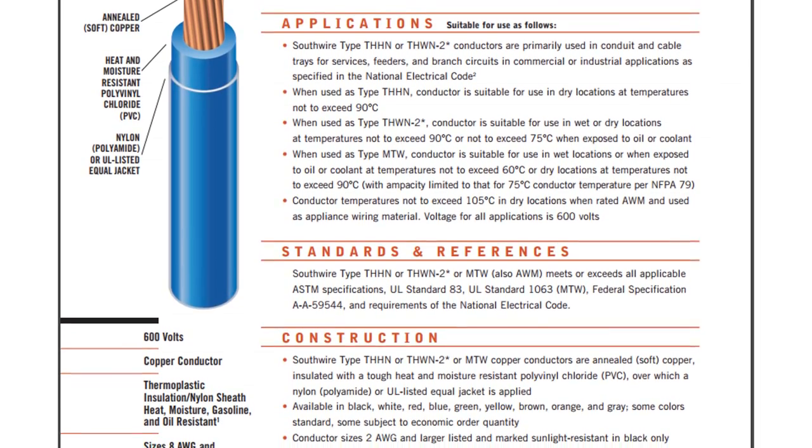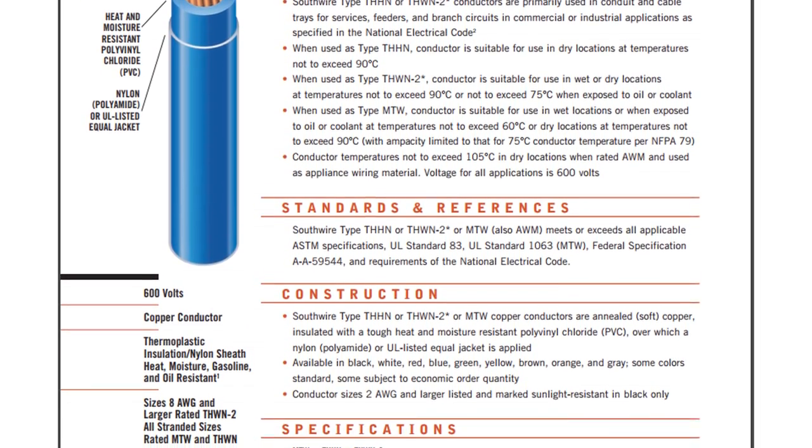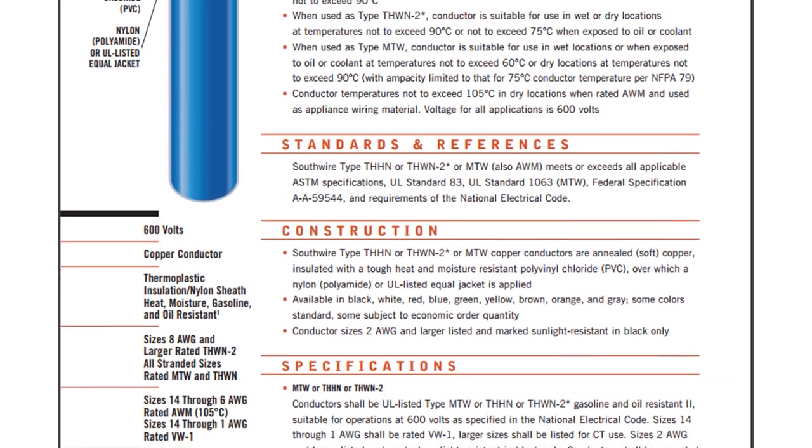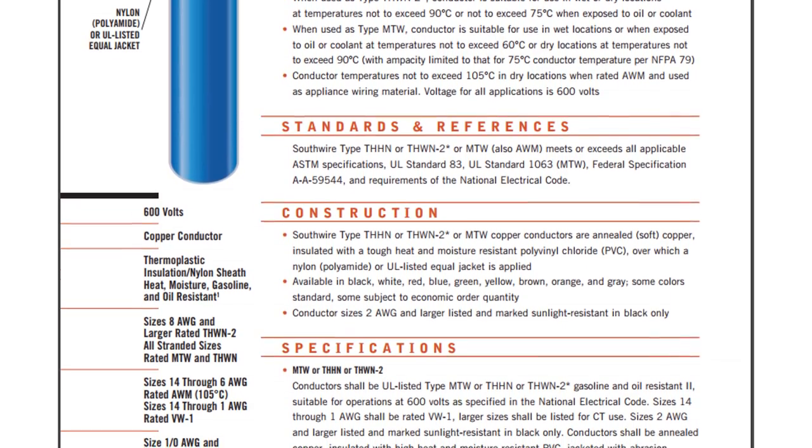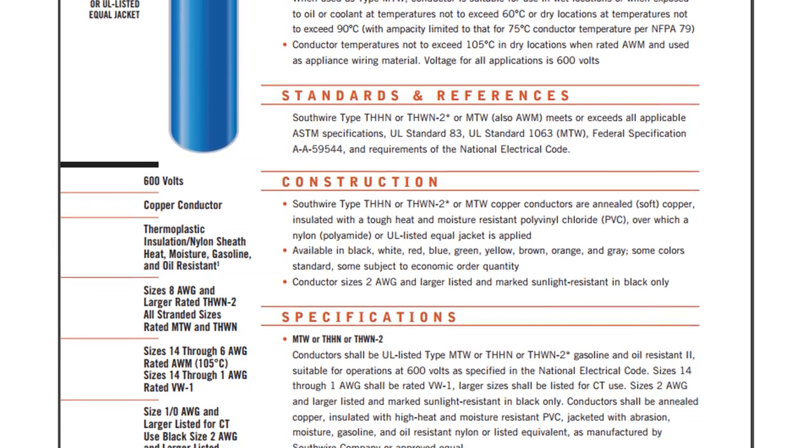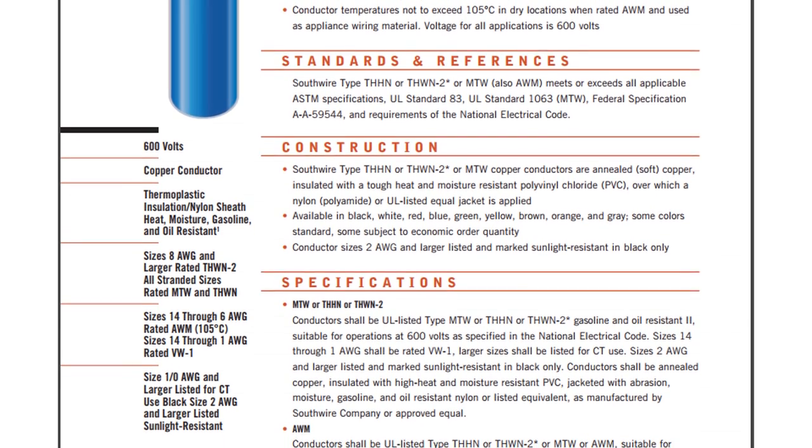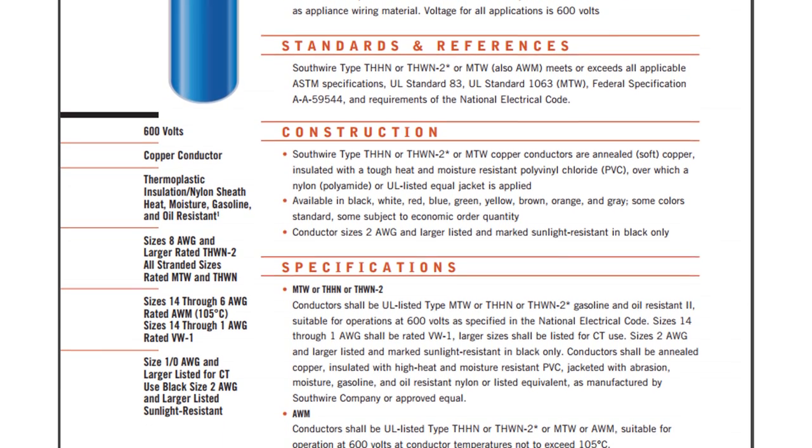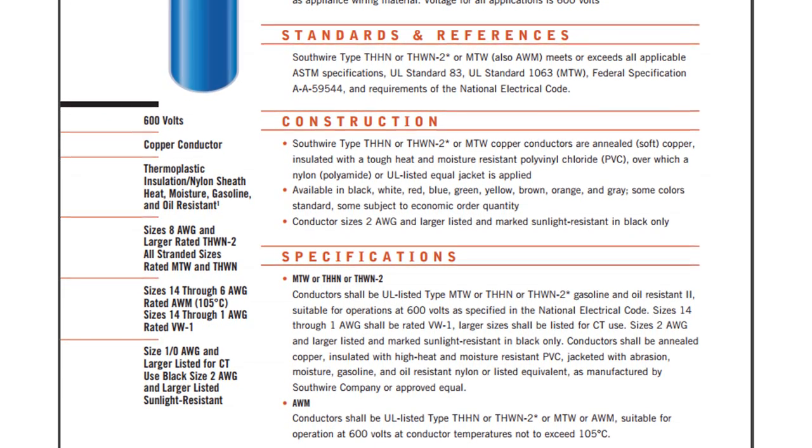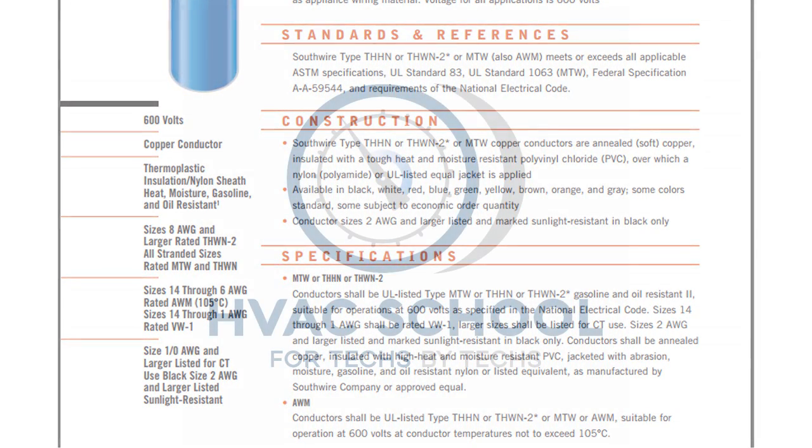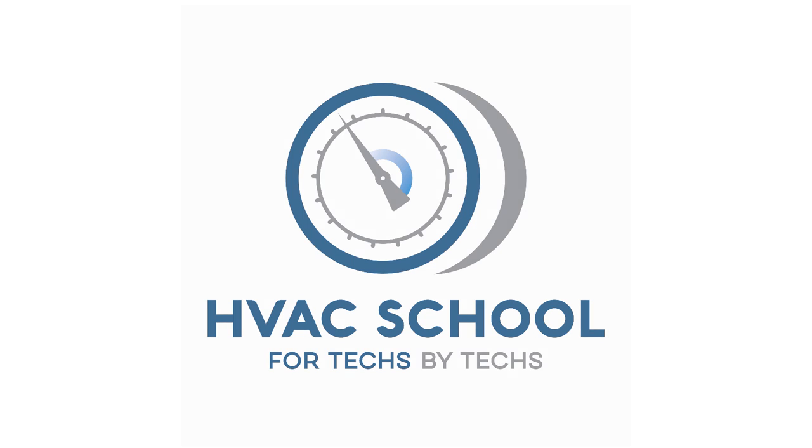Often what we think a wire is rated at is not what the wire is rated at, and it can go either direction. We can be over conservative where we believe a wire is not large enough when it actually is large enough if you look at the insulation rating on the wire. Or we could be grossly undersizing a wire because we don't understand all of the derating factors or the type of wire that it is, or we could be using Romex NM cable in a place that it's not rated for. There's all these different considerations, and often in the field we can be on both sides of the coin where we don't understand either of them. We just think number 10 wire is 30 amps, but it just isn't quite that simple.